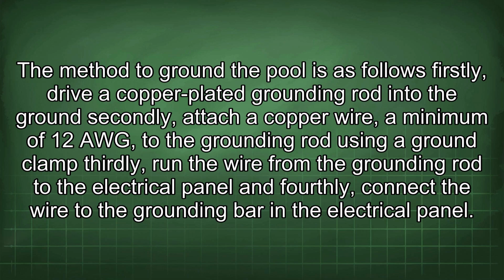Firstly, drive a copper-plated grounding rod into the ground. Secondly, attach a copper wire, a minimum of 12 AWG, to the grounding rod using a ground clamp. Thirdly, run the wire from the grounding rod to the electrical panel. And fourthly, connect the wire to the grounding bar in the electrical panel.